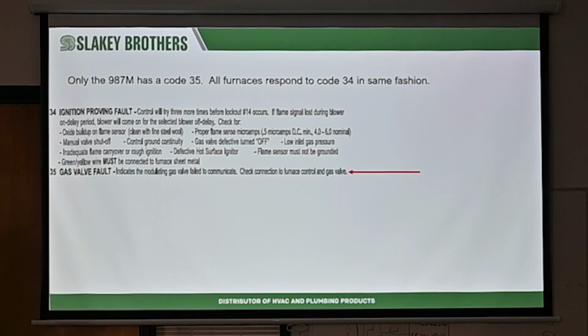Hot surface igniter. Obviously, if you got flame there, it means the hot surface igniter works. So, if your gas valve is on but no hot surface igniter, you got to see if the hot surface igniter is getting power. And again, control ground continuity. You got to make sure you have a really good ground. This one was an easy one.